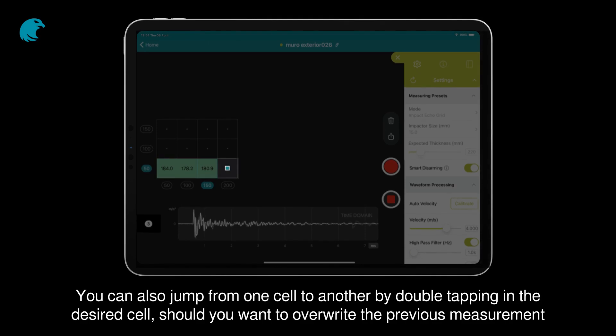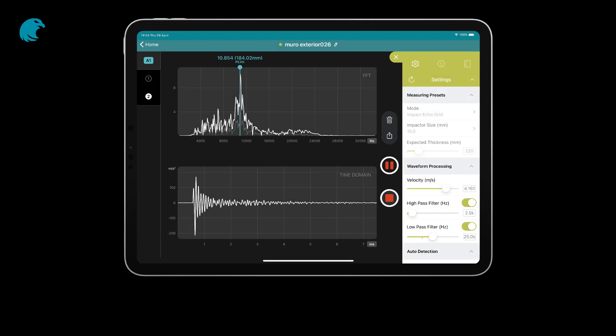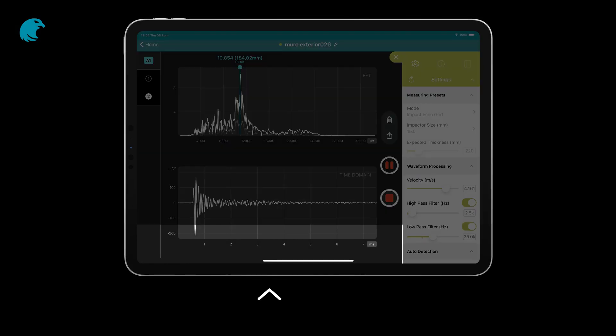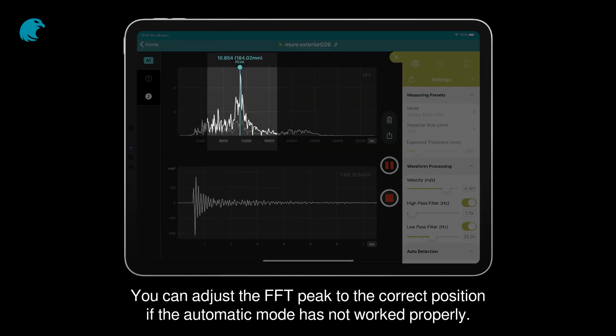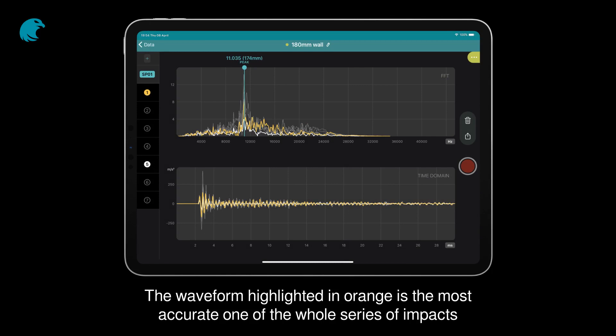You can also jump from one cell to another by double tapping the desired cell, should you want to overwrite the previous measurement. Step 6. Using two fingers, swipe up from the bottom of the app to change from time domain to frequency domain mode. You can adjust the FFT peak to the correct position if the automatic mode has not worked properly. You can navigate from one impact to another by pressing the impact button. The waveform highlighted in orange is the most accurate one of the whole series of impacts.